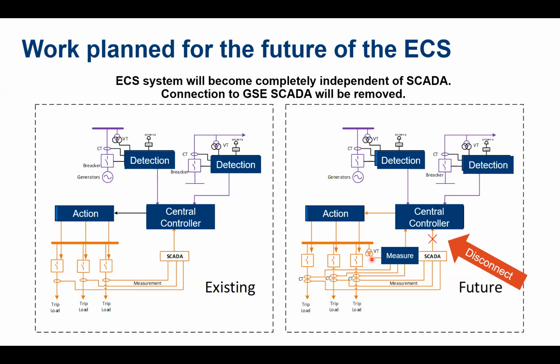Yes, as Vladimir said, we are keeping one connection to the SCADA system today, by IEC 104. This is a connection for the slow information, as we call it. Slow information about the loads for load calculation for load shedding. But practice shows that when the SCADA system fails or SCADA servers are failing, we have a problem in the central ECS system. The calculations are not conducted in the central ECS system, and our ECS system automatically switches over to a distributed system. This is one more reason why protection degree systems and informational degree systems such as SCADA, in our understanding, should be separated. Very good. Thank you.